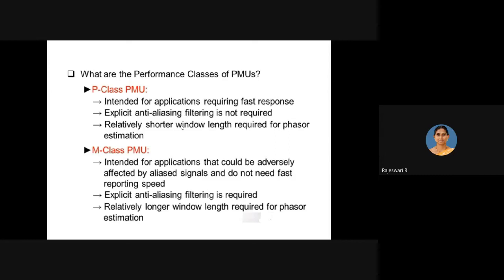So a low pass filter is not needed for this P class type of PMU. Whereas for M class, which is for monitoring purposes, we are very particular about observing the dynamics present in the system. So here the window length is longer, that is, the number of samples in a cycle. Our window is very, very large, near about 200 samples in a cycle, right? Therefore the operation it needs to perform requires filtering the high frequency content. Therefore anti-aliasing filters are required for this M class PMU, right?